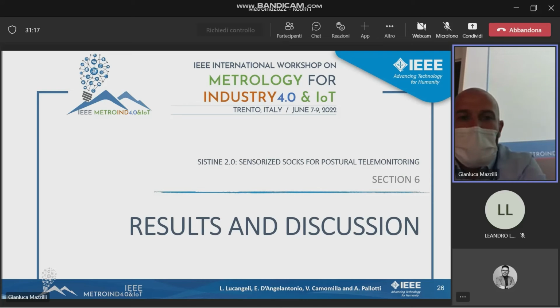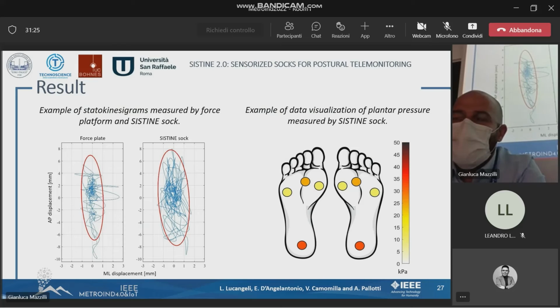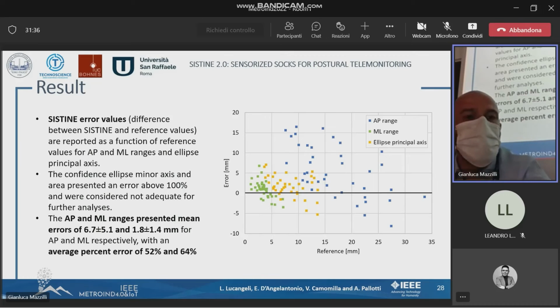For this last section, I present the results. In particular, the data permit to build the images of the COP trend or for the evaluation of plantar pressure. And furthermore, the SISTINE error values for the COP have been calculated and reported in the graph on the right, according to the reference of the force platform. Of the 5 parameters extracted, the minor axis and the area of the confidence ellipse were excluded because they assumed an error value above 100%. For the anteroposterior range, we have an average error of 7 millimeters.